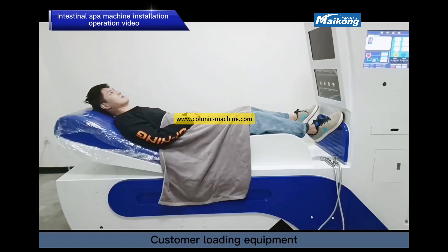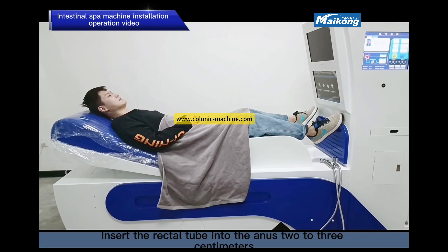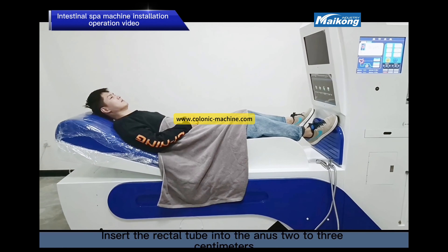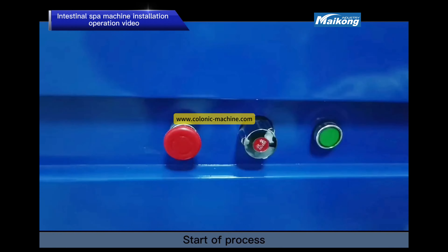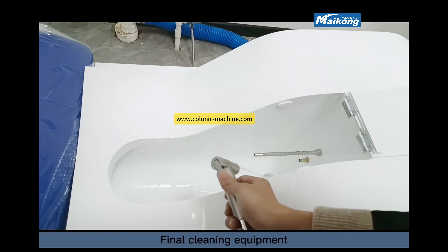Customer loading: have the patient lie flat on the bed in a comfortable position and insert the rectal tube into the anus two to three centimeters. Lift the emergency stop button to start the process, and the device will automatically stop at completion. Finally, clean the equipment.